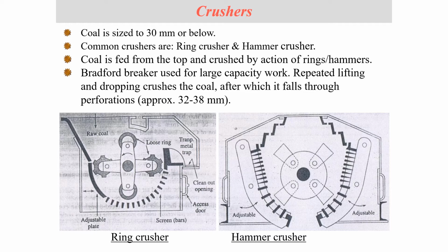So what we do is we actually go somewhere in the middle of using large coal chunks and completely pulverized coal. So what we do is we actually use crushers to make coal pieces of about an inch or smaller in size. So that is still a solid object, actually a full piece of coal, but it is not large enough to actually require minutes or even hours of burning.